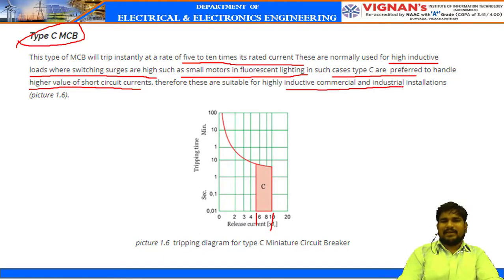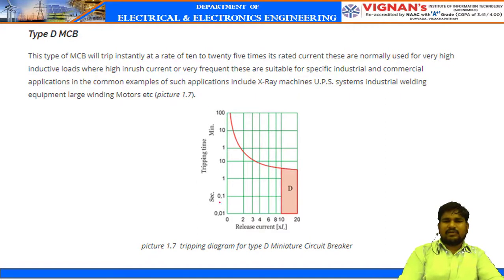Right. This is about type C MCB, which is rated for 5 to 10 times of rated current. And the next one is type D MCB. In this case, it can withstand a short circuit current of 10 to 25 times. It can withstand fault current of 10 to 25 times of rated current.